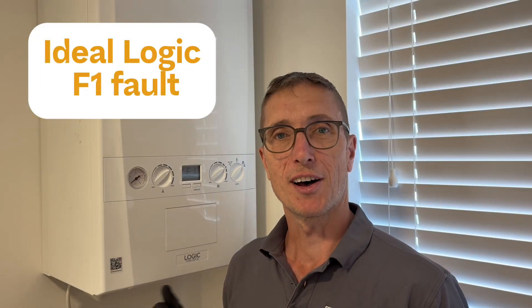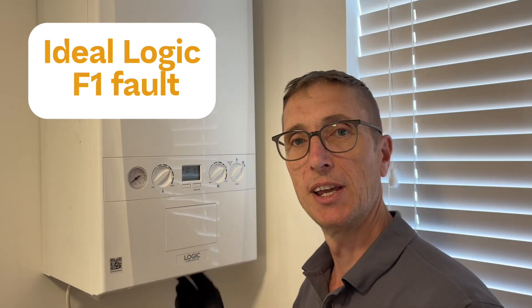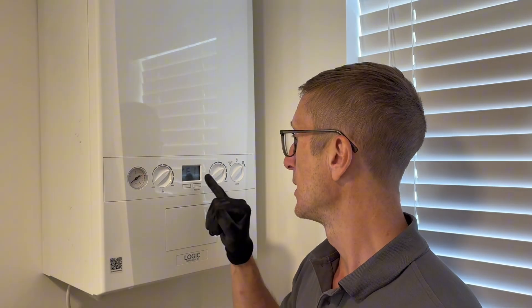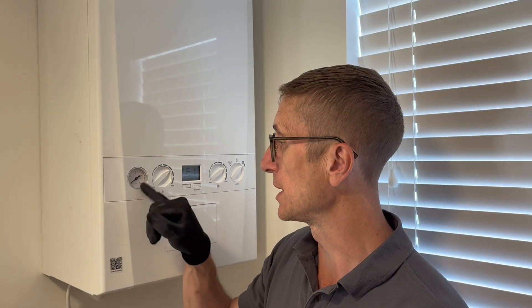To re-pressurize your Ideal Logic combi is quite simple - there are two levers underneath that you have to adjust. We're going to show you how to do that. If your boiler pressure is low, you'll have an F1 fault, which we've got here, and on the gauge that'll be showing down to around zero bar. When that occurs, it's time to top the pressure up.